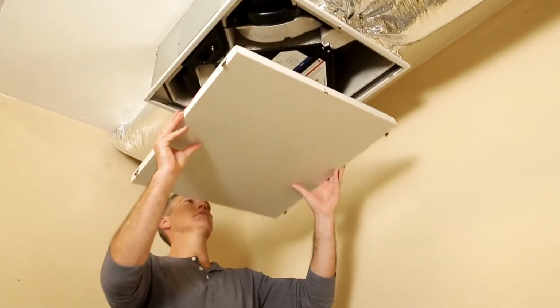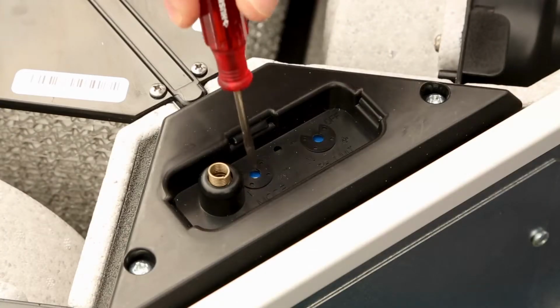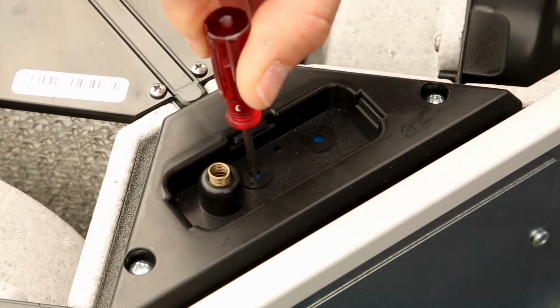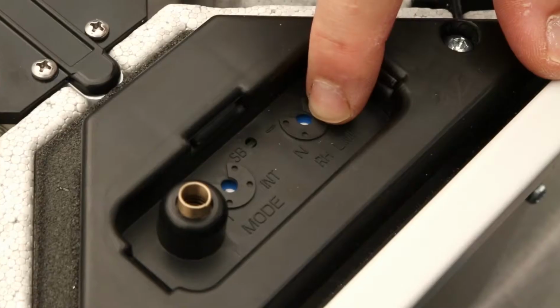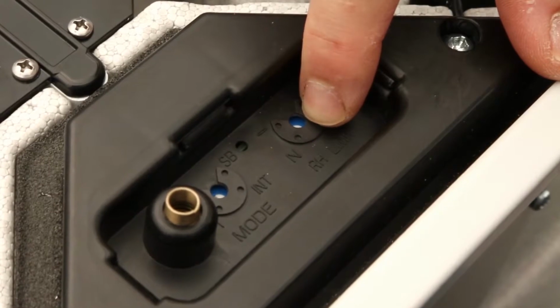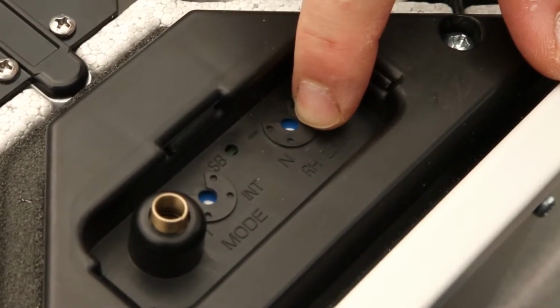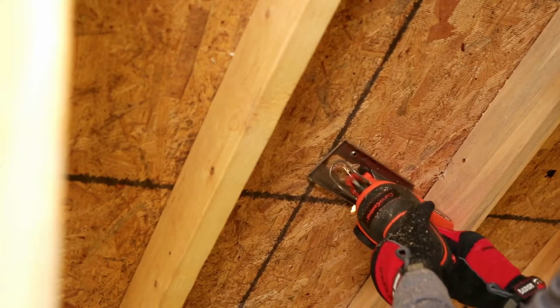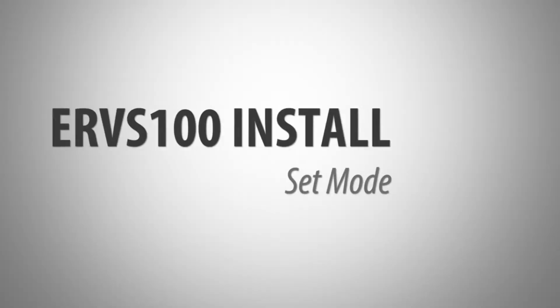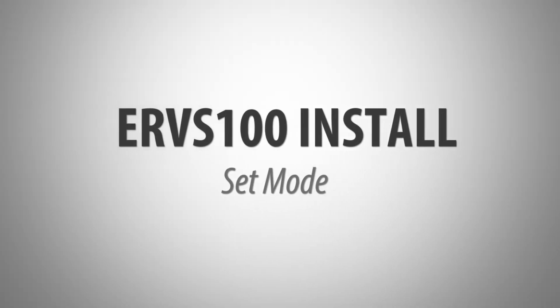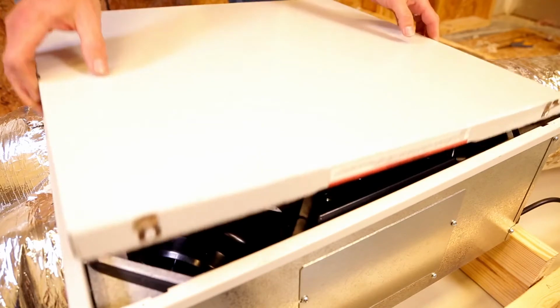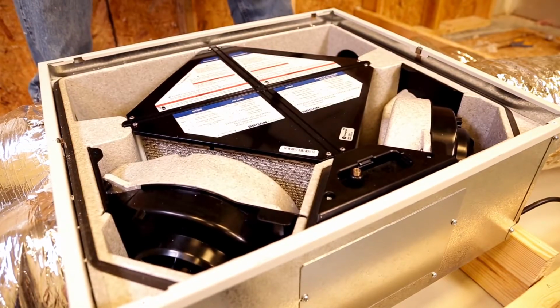Once the unit is installed and construction is complete, you will want to adjust the unit's controls to the appropriate settings. The unit ships with factory settings in standby mode and with the N humidity setting. Never run the unit while the building is still under construction. Remove the door to access the mode and RH controls.